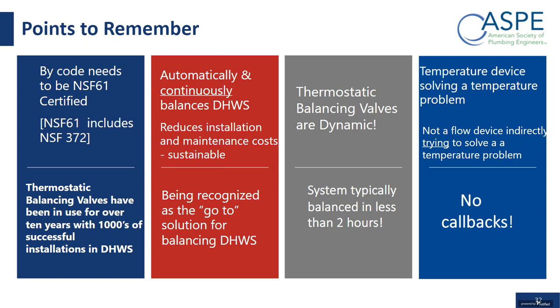It's really strongly being recognized as the go-to solution for balancing domestic hot water systems. It's dynamic. It changes as conditions change. Again, a system is typically balanced in less than 2 hours. It's a temperature device solving a temperature problem, not a flow device trying to solve a temperature problem. Contractors love it because of no callbacks.